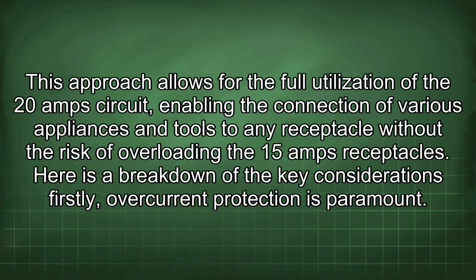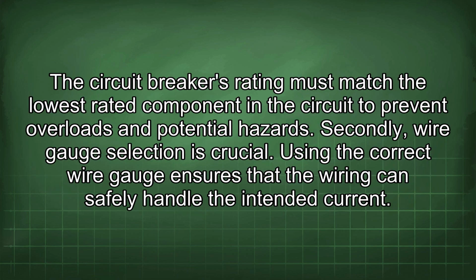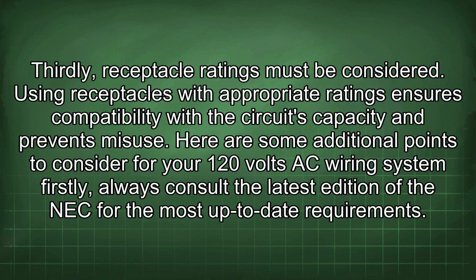Here is a breakdown of the key considerations. Firstly, overcurrent protection is paramount. The circuit breaker's rating must match the lowest rated component in the circuit to prevent overloads and potential hazards. Secondly, wire gauge selection is crucial. Using the correct wire gauge ensures that the wiring can safely handle the intended current. Thirdly, receptacle ratings must be considered. Using receptacles with appropriate ratings ensures compatibility with the circuit's capacity and prevents misuse.